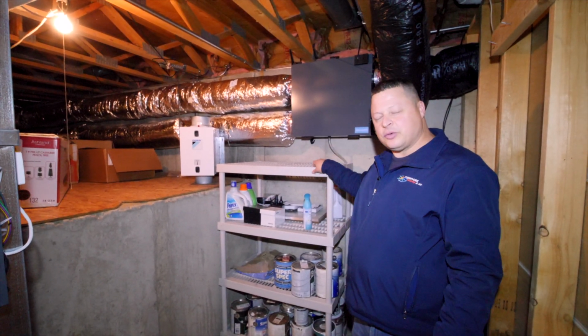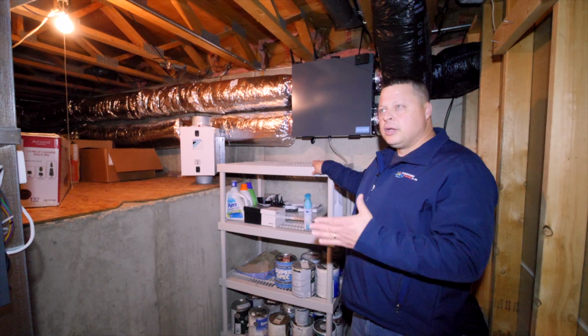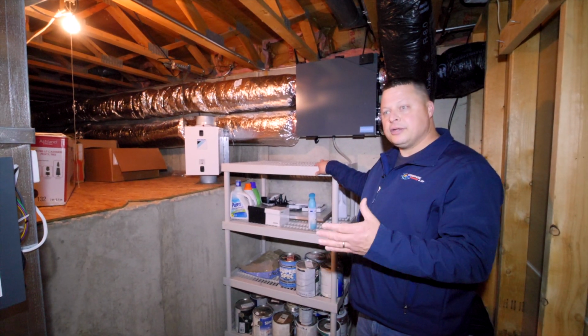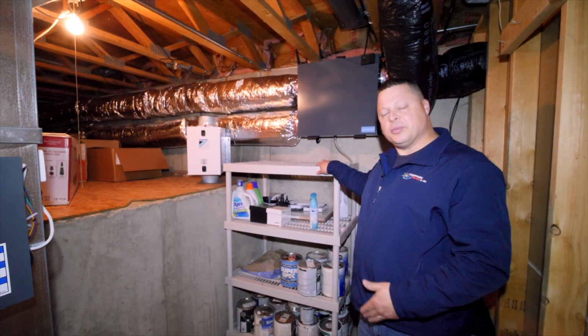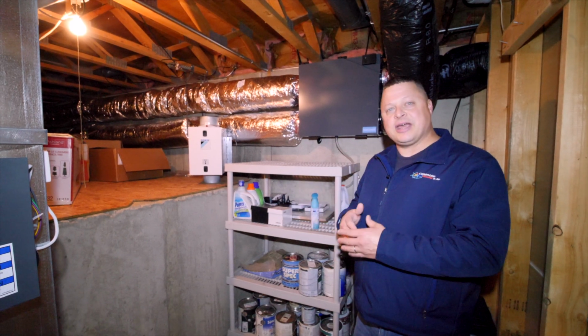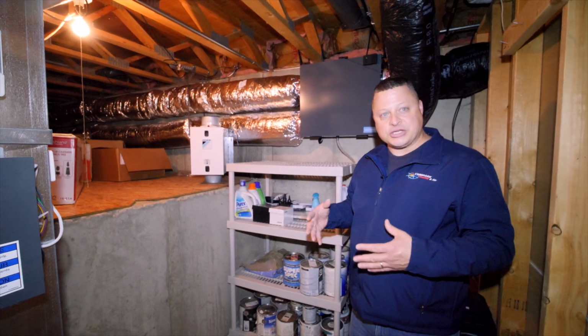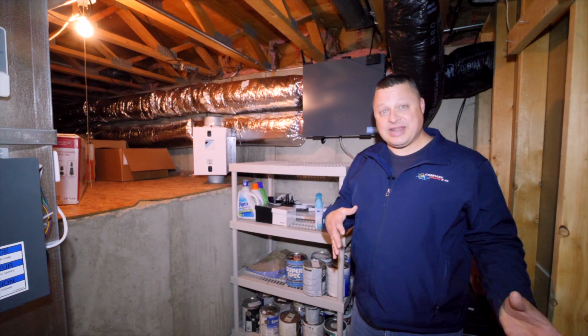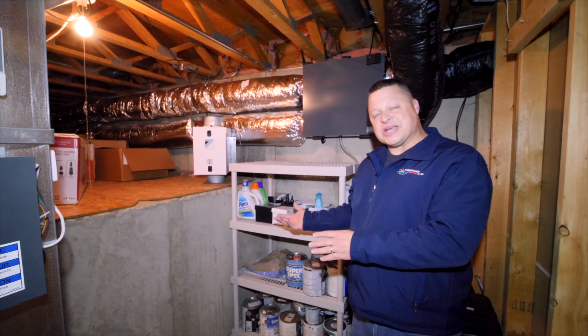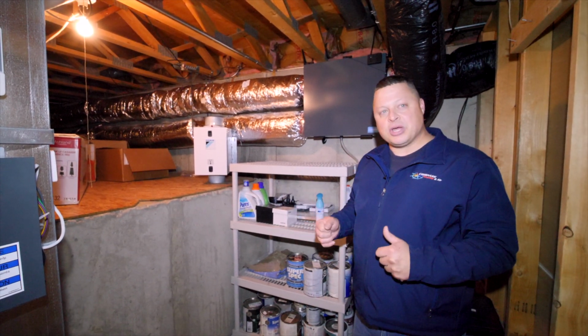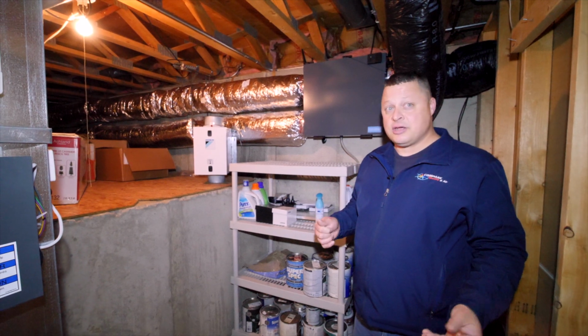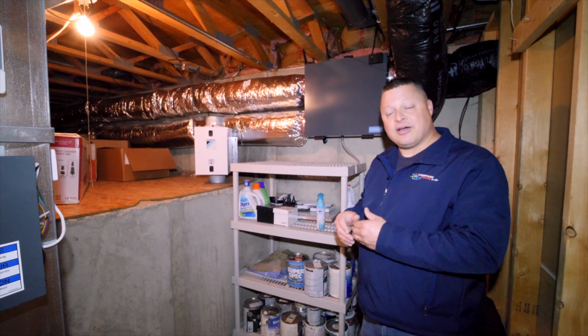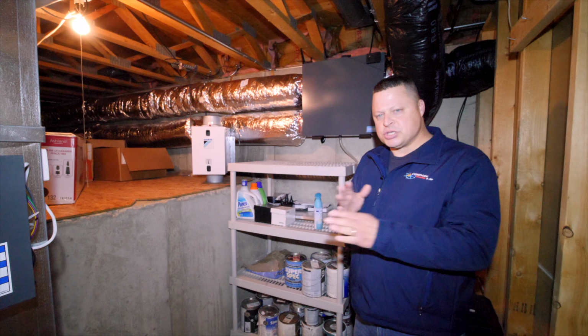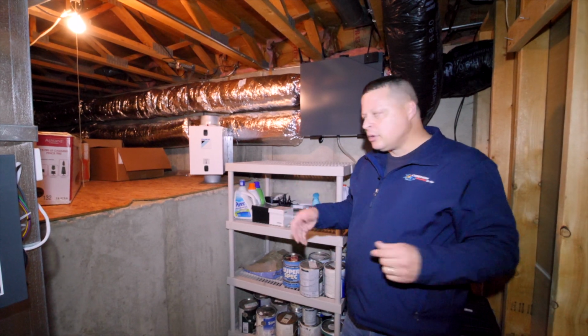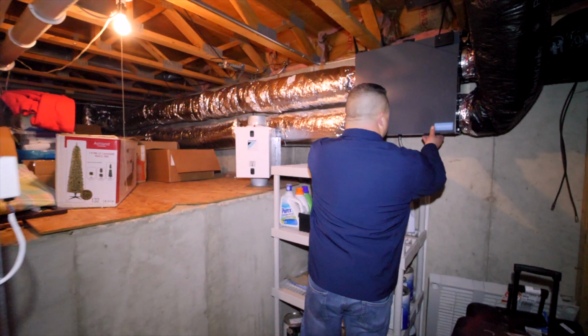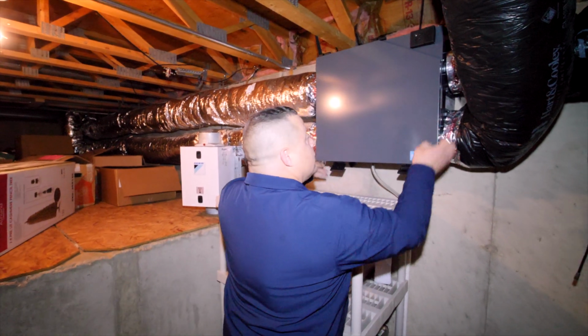I'll open it up so you can see what it looks like inside as well. The core on an HRV is all metal, where this one is a material, and it allows heat and humidity to be exchanged. Therefore, you're able to keep the humidity in the house, or in the summertime, less humidity will come and be introduced into the house with an ERV. With the HRV, we have just exchanging the heat in there. So if you want to take a look in so you can see what they look like.